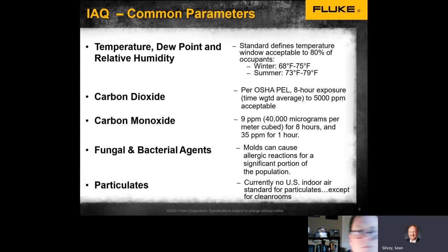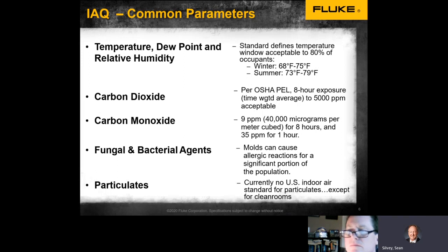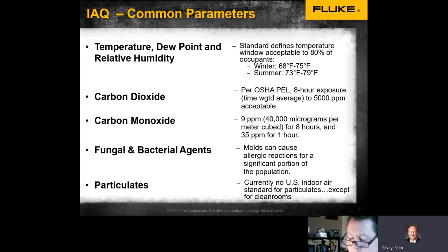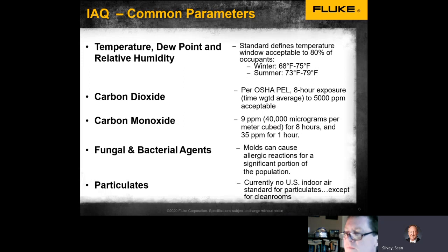For temperature, there are comfort zones for people in a given area. For carbon dioxide, you don't want to be above a certain limit. For carbon monoxide, you typically want zero, but you could have up to nine parts per million over an eight-hour period. Carbon monoxide is the silent killer — we never want that to be very high. There are always fungal and bacterial agents in the air, as well as particulates. On a sunny day in the west, you can see all the particles when sunlight shines through.